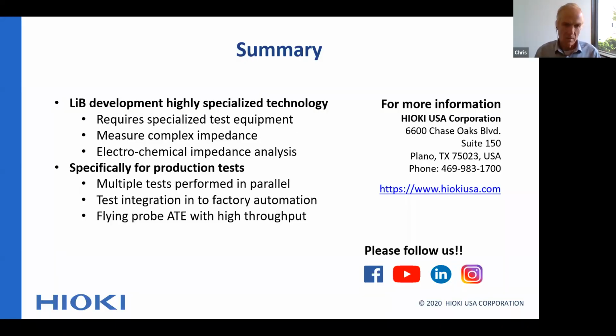So we talked about battery testing at the end of the production line, at the EOL. It requires very specialized equipment, so very specialized tests. We talked about the various tests that you can do for measuring the state of the assembled battery, the internal resistance tests. Those are not simple resistance tests, but complex impedance tests that measure the real and the imaginary value of the impedance over frequency, with specialized test instruments for that, either battery testers or electrochemical impedance analyzers. We also talked about very specific tests that have to be done when you are talking about production.